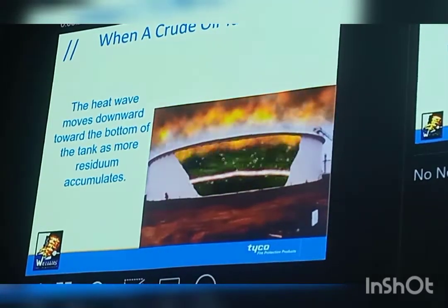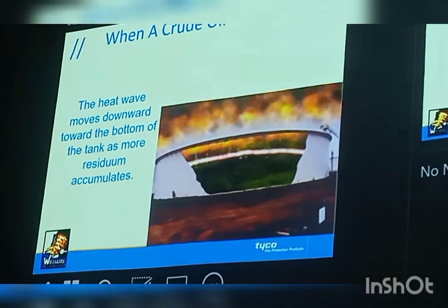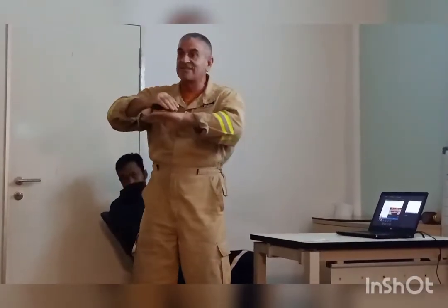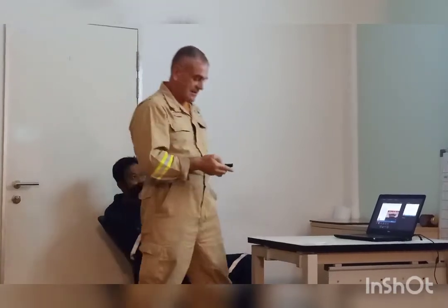Does that make sense? So, hot, light elements, gas burns, generates more heat. The thick elements get hot, increases more, sinks down, heats up the cold oil, more gas release, more heavy elements added to the thermal layer, and it works its way down.